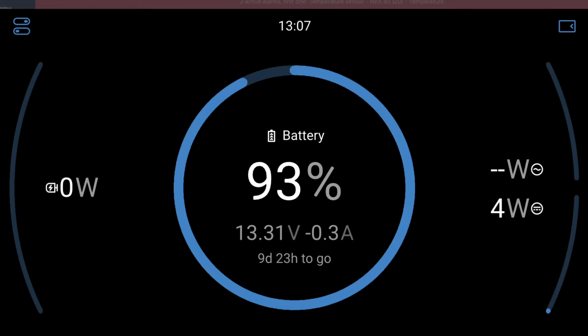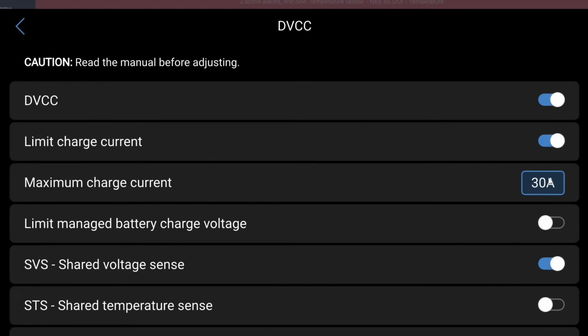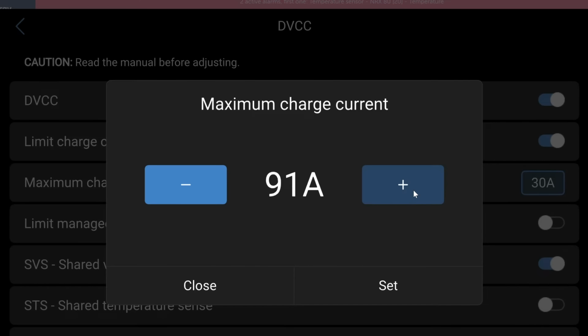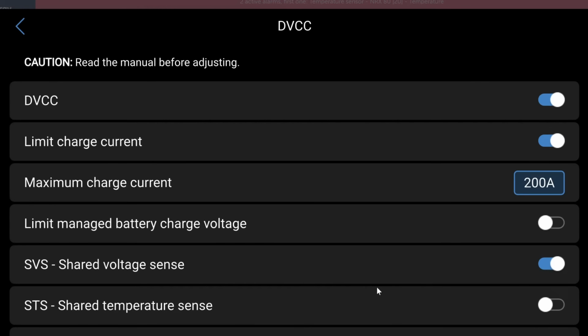So you can see how sizing your battery bank for throughput, in addition to storage, is so important when designing a system. In this scenario, you could use the limit charge current feature of DVCC to, well, limit the charge current across the entire system so that all the chargers never exceed 200 amps.